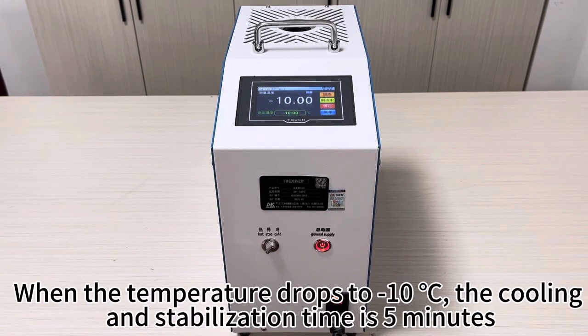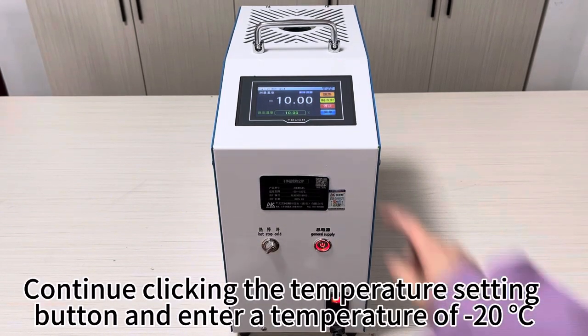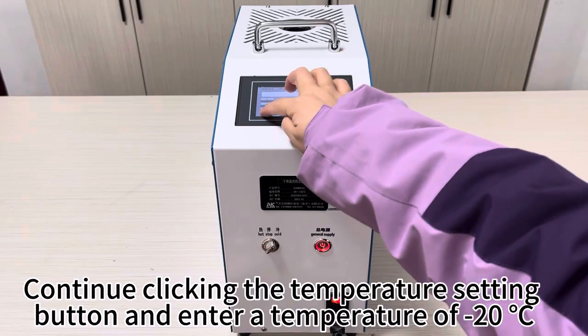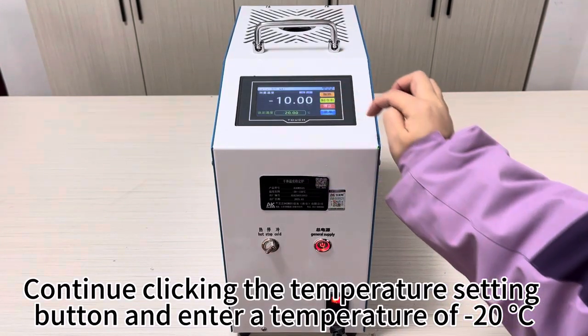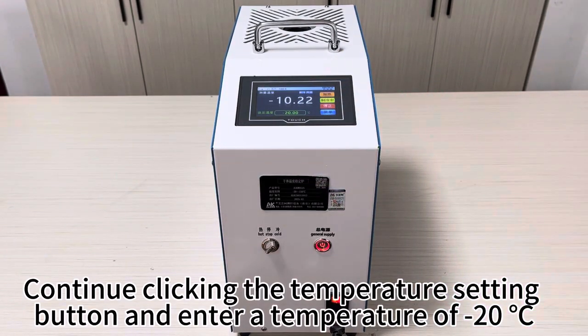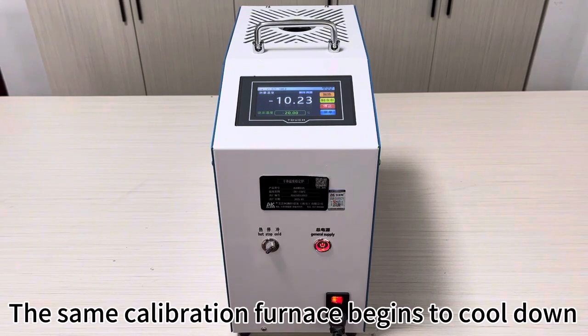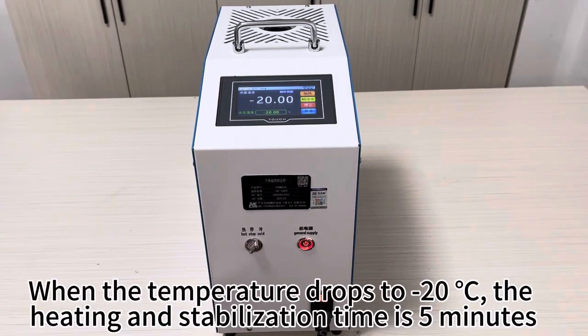When the temperature drops to -10 degrees Celsius, the cooling and stabilization time is 5 minutes. Continue clicking the temperature setting button and enter a temperature of -20 degrees Celsius. The same calibration furnace begins to cool down. When the temperature drops to -20 degrees Celsius, the stabilization time is 5 minutes.